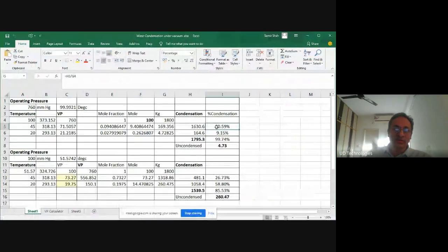Like this. With the cooling tower, it is 90.59. There will be 9 more overall with this utility, it will come around 99.74, meaning around 1% is lost. And if we go under vacuum, I have taken this under vacuum also. If we apply the vacuum at 100 mm Hg, the boiling point will be 51.574. I have considered this with the cooling tower and the chilled water. So overall, when we talk about the vacuum, cooling water only condenses 26.73%, and chilled water increases it by 58.80%. So overall condensation is only 85.53. Now we will see how vacuum control will help you increase the condensation.